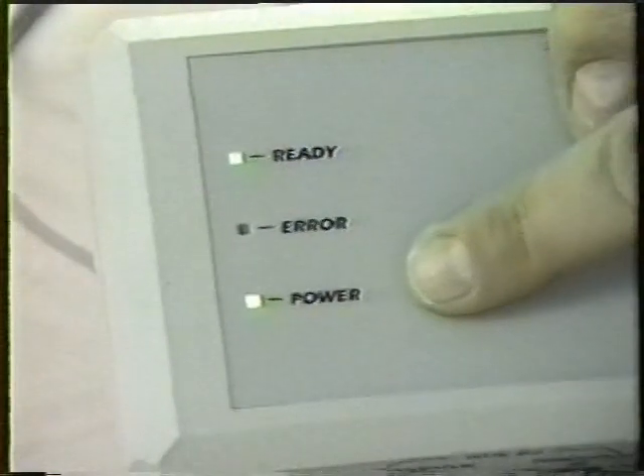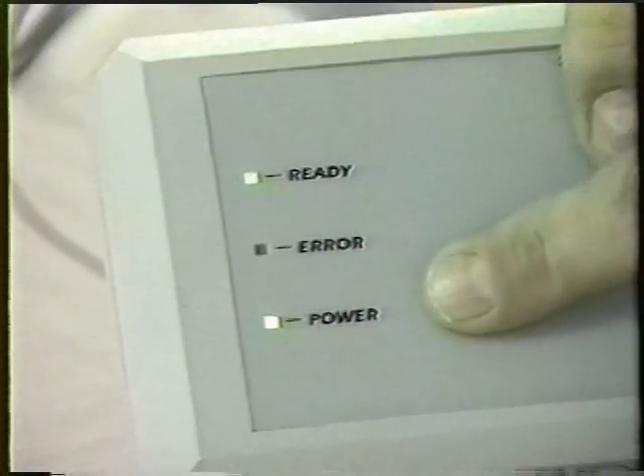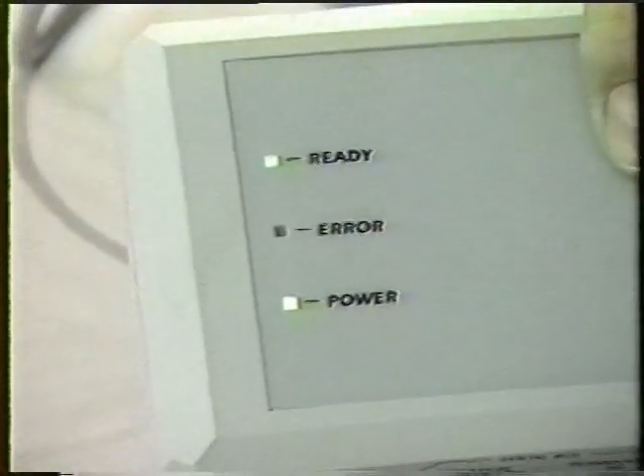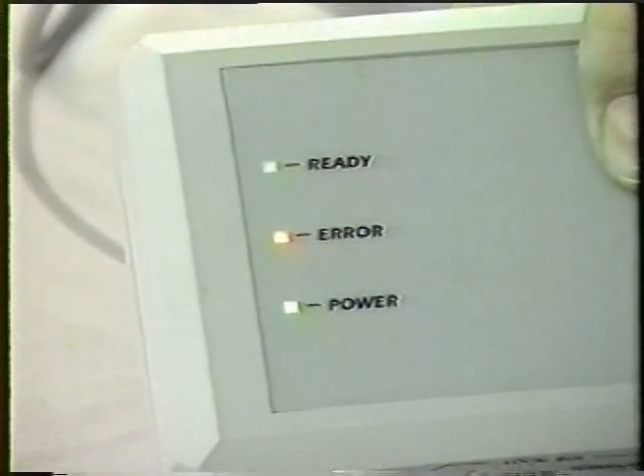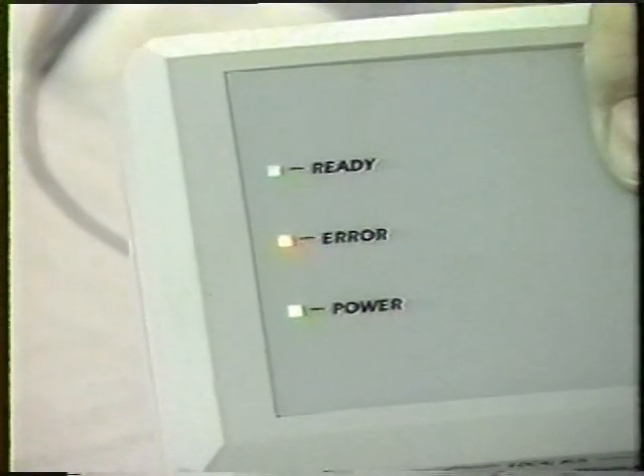What I want to do is show you an immediate way of troubleshooting these lines. Watching the ready light here, watch what happens when I disconnect the equipment that's connected into this. See the light flashing once per second? This is an indication of a CPE failure — customer premises equipment failure — one flash per second.